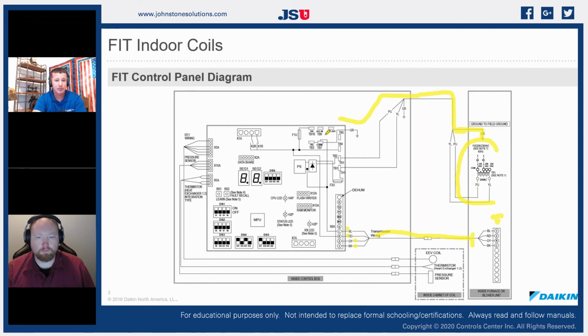And when it gets up here to that EEV, we're going to notice that common from our furnace transformer makes its way through this control board, lands on common of the board, and is grounded. So grounding of this entire network is just absolutely critical. If we have a system that is not communicating properly, the very first thing that we need to do is verify that we have proper grounds throughout our entire network. So very first thing, verify that we have grounds.